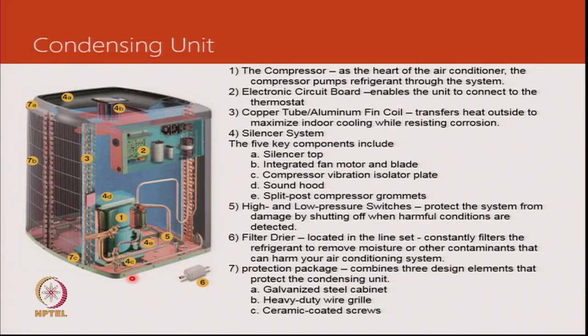There is a certain repeat in component to component, and you can see the condenser coil circuiting on this side. So one end of the coil would have headers, finally connecting it to a discharge tube, and the other end would be the liquid line which would go to the split system, the other end of the split system. This is the hairpin side of the bent condenser.